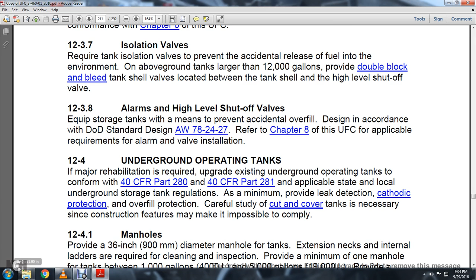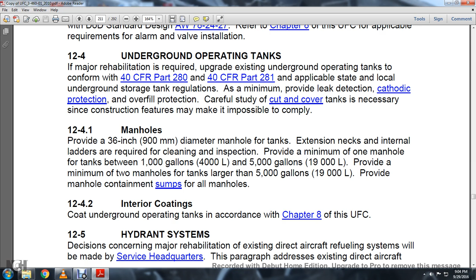12.4.1 manholes. Provide 36-inch diameter manhole for the tank. Extension necks and internal ladders are required for cleaning and inspection. Provide minimum of one manhole for the tank between 1,000 gallons and 5,000 gallons. Provide minimum of two manholes for the tank larger than 5,000 gallons. Provide manhole containment sumps for all manholes. 12.4.2 interior coatings. Coating of underground operating tanks are in accordance with the Chapter 8 of the UFC.